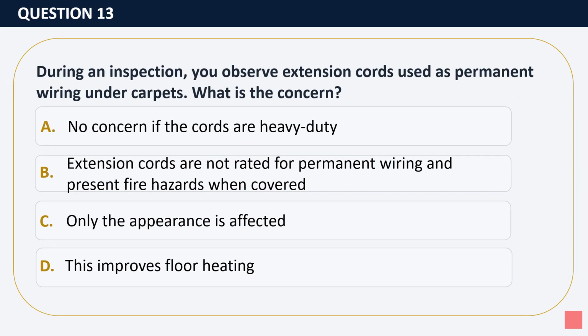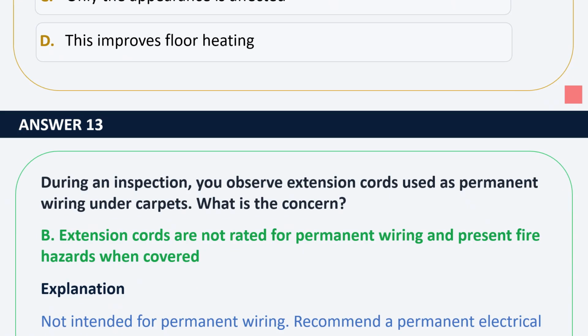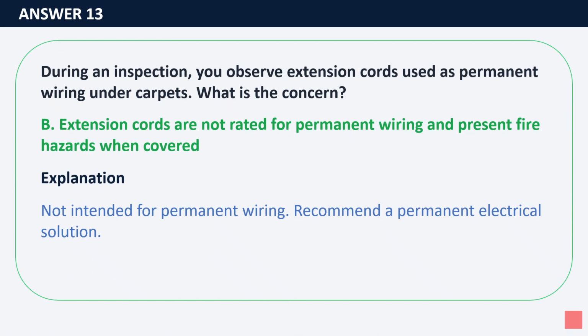Question 13. During an inspection, you observe extension cords used as permanent wiring under carpets. What is the concern? A. No concern if the cords are heavy-duty. B. Extension cords are not rated for permanent wiring and present fire hazards when covered. C. Only the appearance is affected. D. This improves floor heating. Answer B. Explanation: not intended for permanent wiring. Recommend a permanent electrical solution.